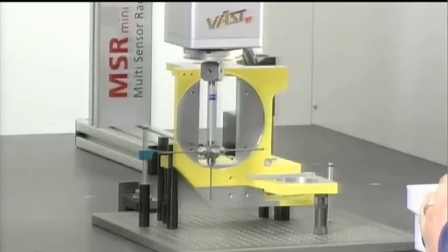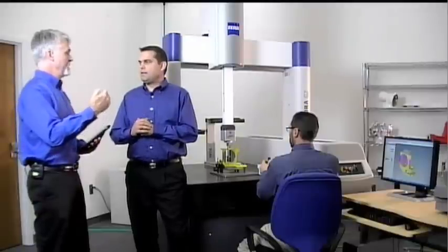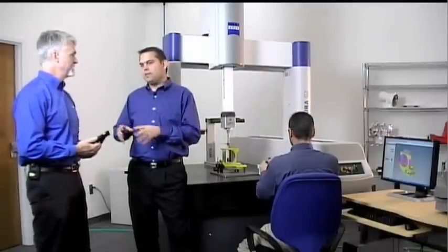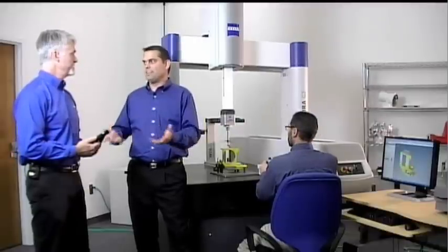Okay. Now, when you say upgrade, is that loading Calypso on their computer that's on their legacy machine, or is this a completely new system, or what's the deal? It could be not always working well because the older legacy software is running in DOS or something older. Calypso is running in Windows 7 or XP, and we typically just have a separate computer installed. Okay, so they basically don't have to touch anything about their old software or old computer. You're basically, if you need to, hooking up a new computer with the Calypso on it. Yeah, every controller has a different type of connection. Some of them are serial connections or a LAN connection. So the cable itself, we could put an AB switch to jump back and forth.